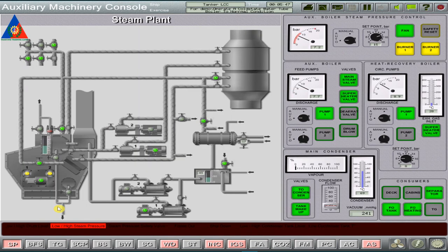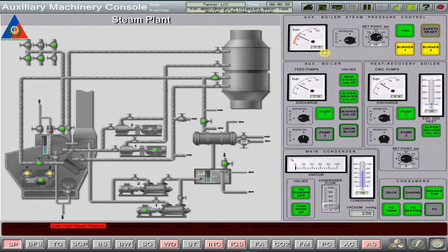The normal operating pressure of the auxiliary boiler must be above 10 bars to a maximum of 18 bars for the low pressure steam alarm to be cancelled out or rectified.